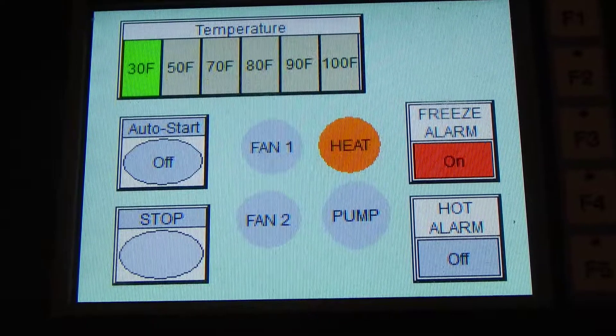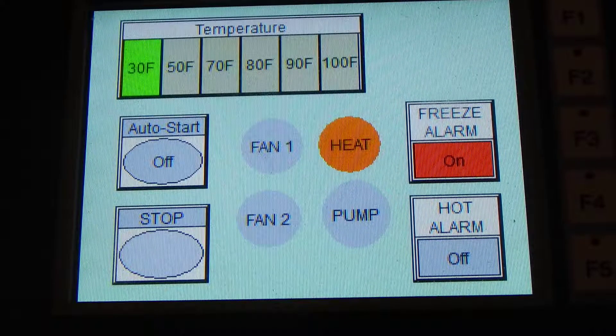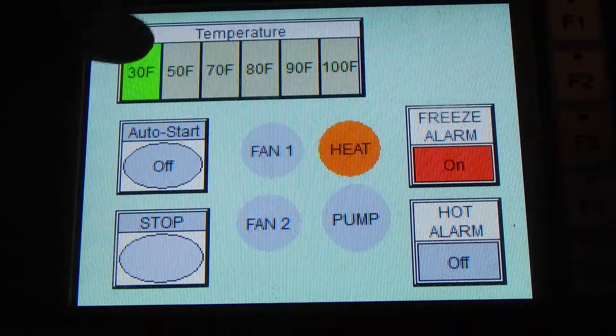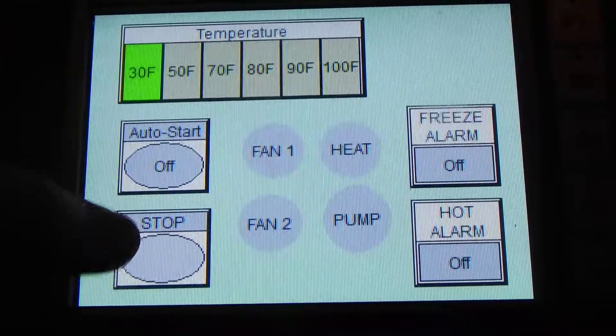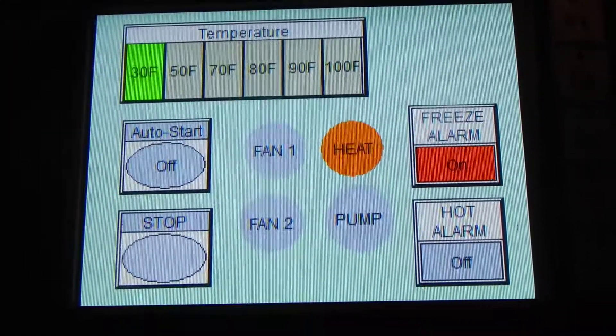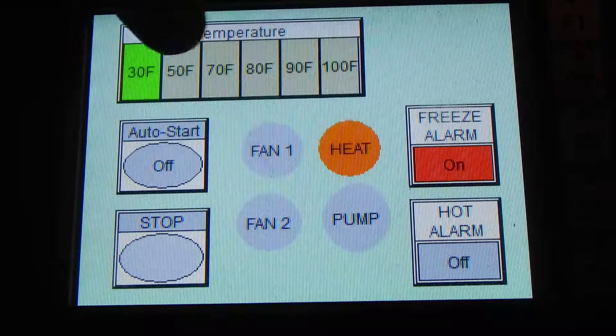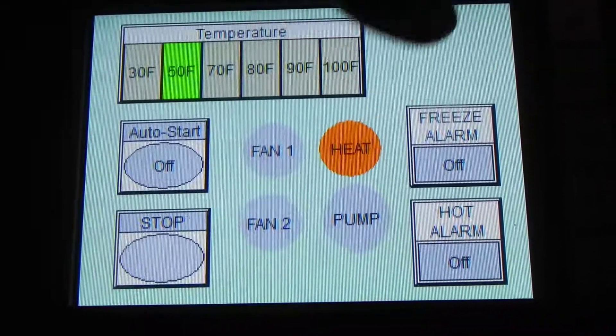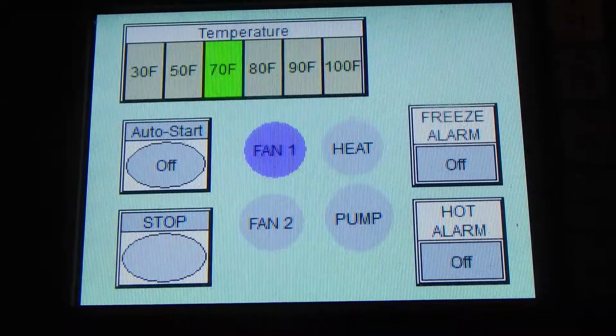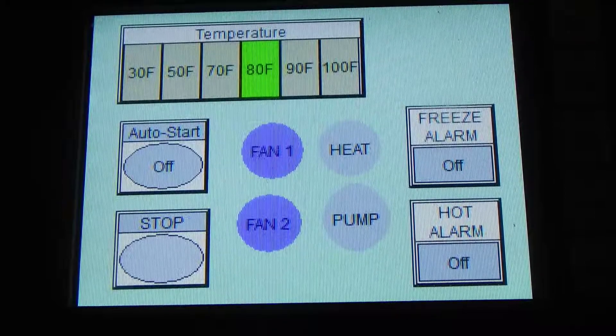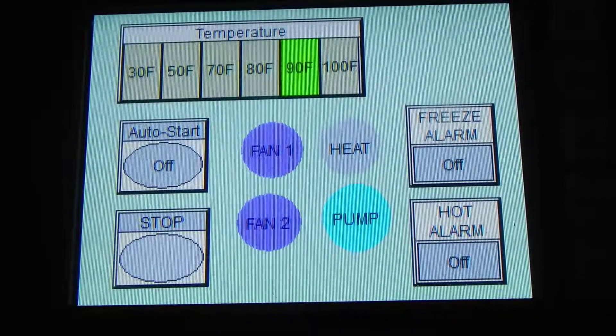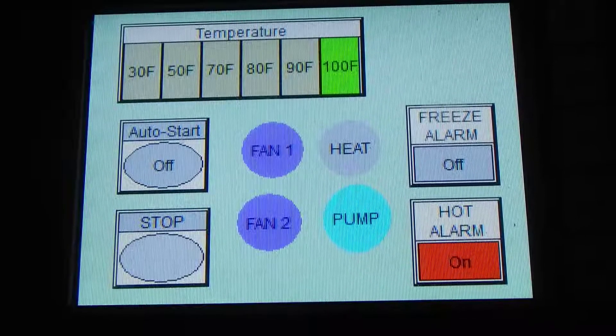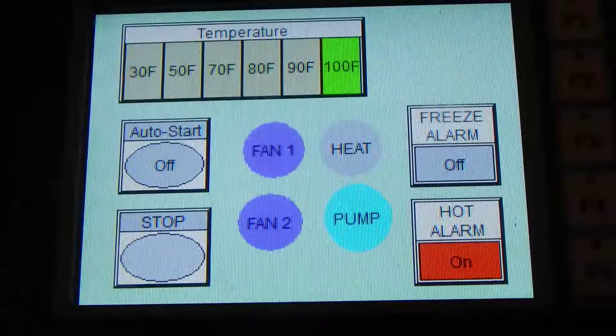Here we have our PLC and the OIT for the first project for our greenhouse. 30 degrees, let's turn it on. Turn it off and we should lose everything. Let's turn it on, 30 degrees, we're going to get a freeze alarm and heat. 50 degrees, we're going to get a heat, no alarm. 70, we should have fan 1 on. 80, we should have fan 2 on. 90, we should have both fans in the pump. And 100 degrees, everything should be on and we get a hot alarm. Perfect.